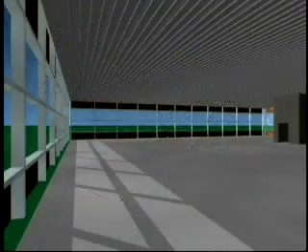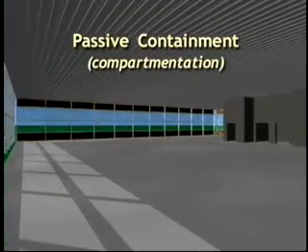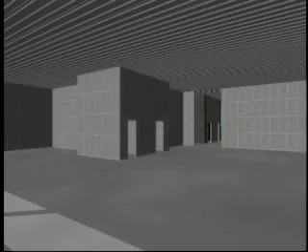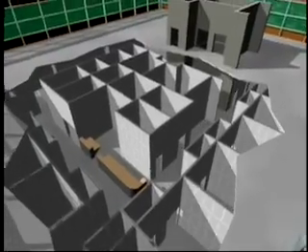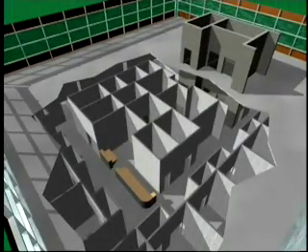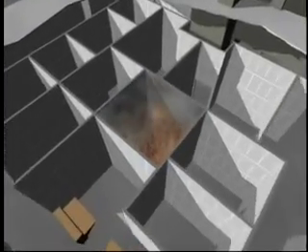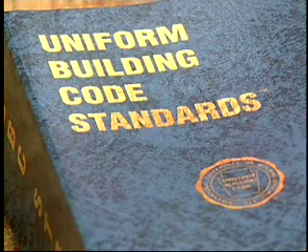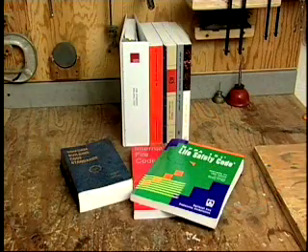The third and final goal is passive containment, sometimes known as compartmentation. It's intended as a last resort should both prevention and suppression fail. Passive containment is accomplished by dividing building space into smaller compartments that are designed to minimize the spread of smoke and fire. These compartments will neither prevent nor suppress a fire, but will contain it to prevent horizontal or vertical spread of flames, heat, smoke, and toxic gases. The NFPA Life Safety Code and all model building codes in North America mandate compartmentation in health care facilities due to the need for defending in place in a fire.